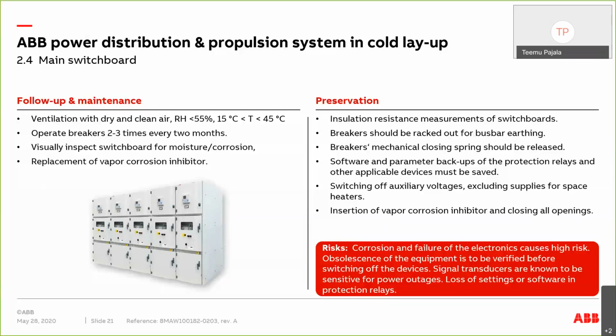For the protection relays, software and parameter backups need to be taken again to have the latest situation, what it was when the system was switched off. Otherwise, all auxiliary voltages can be switched off, but the space heaters again need to be on.